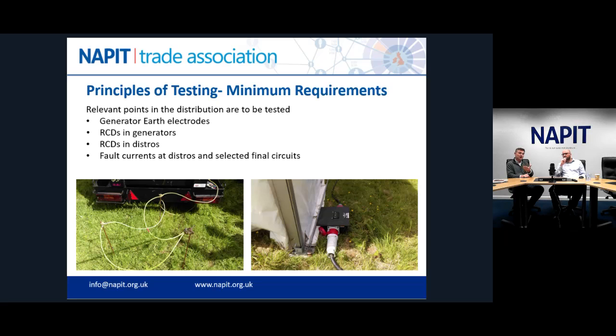The RCDs, again, we'd want to check that they're working effectively. Now, quite often the variable ones will have a test feature on them, so you can actually make sure that they are operating effectively. And BS 7909 encourages at the very least that you go around all the distribution units pressing the test button on the RCDs to make sure they're functioning, because mechanical damage does happen, and particularly on 30 milliamp devices which are being used for protection against electric shock and additional protection, it's important to make sure that they haven't fallen apart on the way over. It's quite a harsh environment as well, lugging the gear into the event, out of the event, they get thrown on trucks and everything, so you know they are subject to wear and tear.